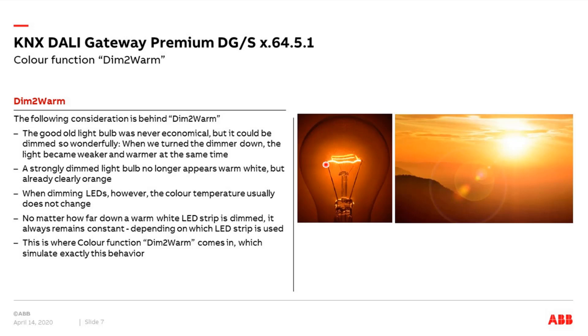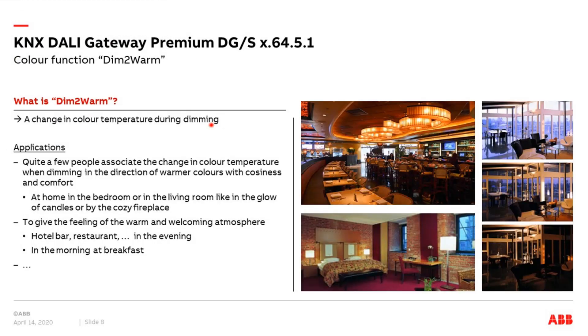Some customers, especially in the residential market, want exactly this feature of a historical light bulb or halogen lamp — when we dim down, the color temperature should change to warm light. With our DALI gateway, we can simulate this using DALI devices. Dim2Warm means when we dim darker or brighter, the color temperature changes automatically. This is also a parameter in the ETS where we can enable, disable, or always-enable it. A typical application is in residential settings like family homes with candles or cozy fireplaces, or in public buildings like hotels and restaurants for a warm welcome feeling.